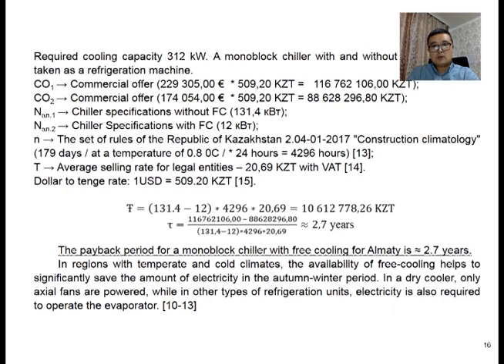A monoblock chiller with and without a free cooling system was taken as the refrigeration machine. The payback period for a monoblock chiller with free cooling for Almaty is 2.7 years. In regions with temperate and cold climates, the availability of free cooling helps to significantly save the amount of electricity in the autumn-winter period. In a dry cooler, only axial fans are powered, while in other types of refrigeration units, electricity is also required to operate the evaporator.